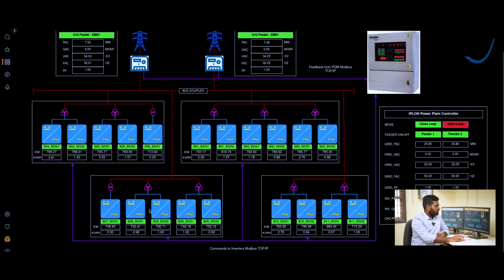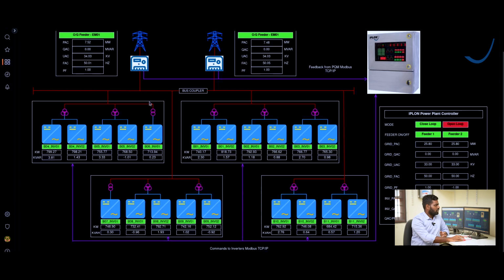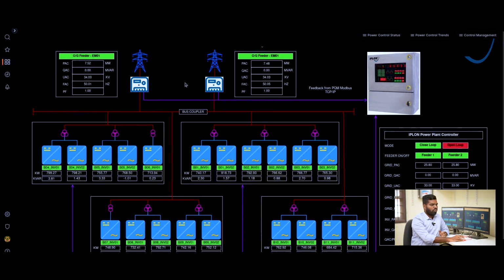Here, these are the inverters for this 50 megawatt site. 20 inverters are there. 11 blocks are there. Each block has 2 inverters. These 11 blocks are connected to the 4 incomers. 4 incomers are connected to the 2 outgoing feeders. This is the site structure. This outgoing feeder level is 33 kV. Here, the inverter level is 0.66 kV to 33 kV. Here are the 2 energy meters of the outgoing feeders.